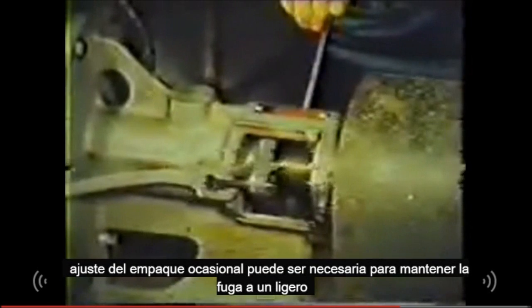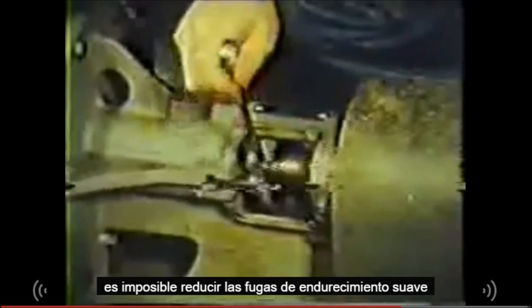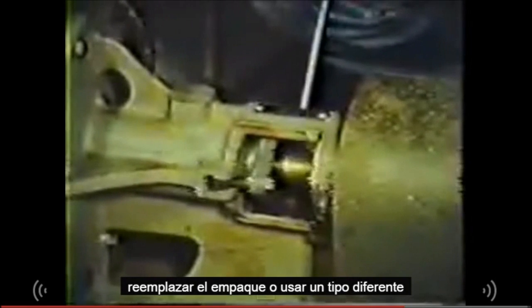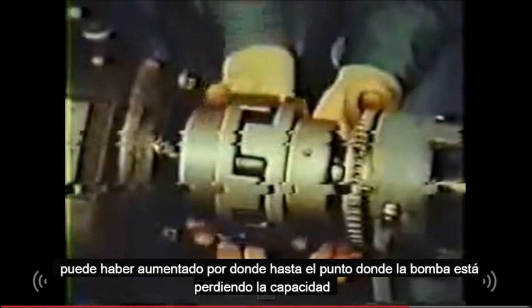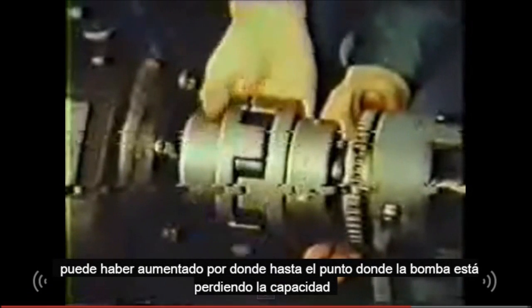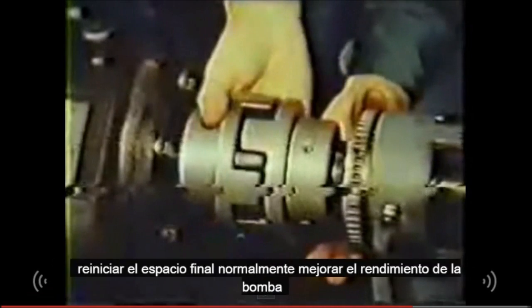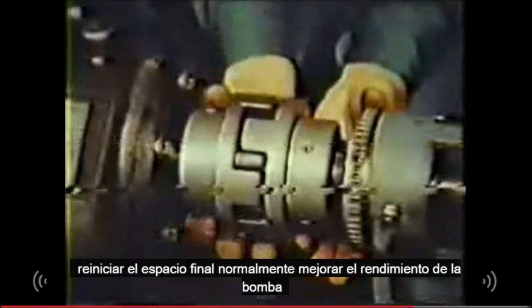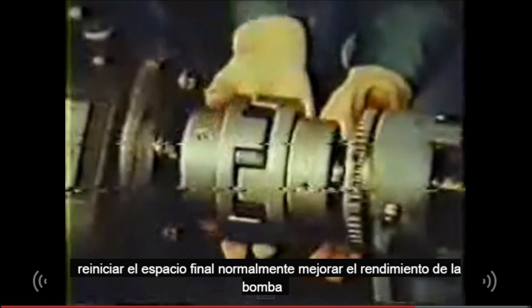Occasional packing adjustment may be required to keep leakage to a slight weep. If impossible to reduce leakage by gentle tightening, replace the packing or use a different type. After long service, the running clearance between the end of the rotor teeth and the pump head may have increased through wear to the point where the pump is losing capacity or pressure. Resetting the end clearance will normally improve pump performance.